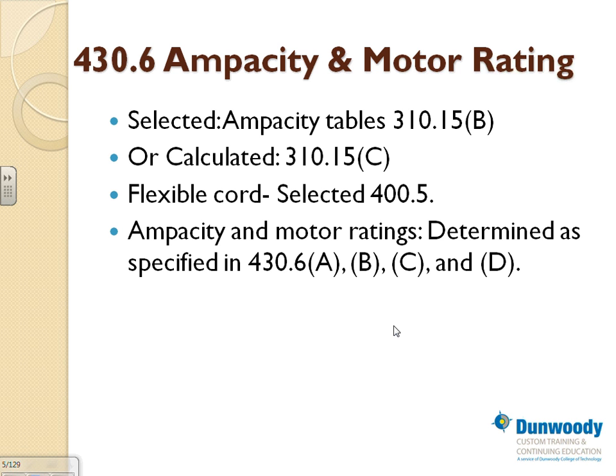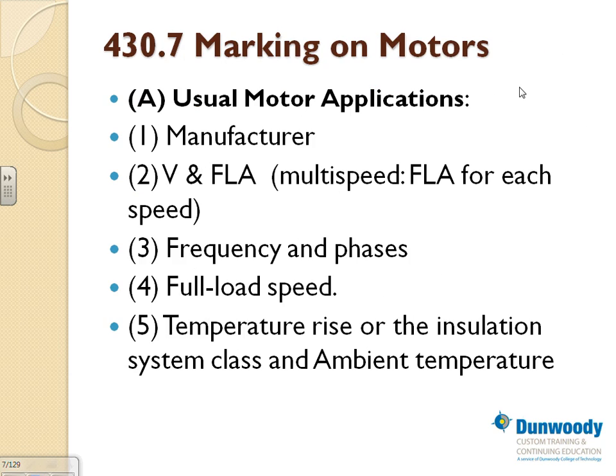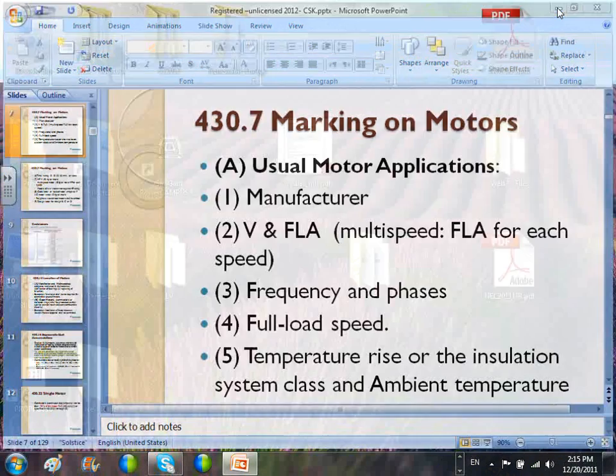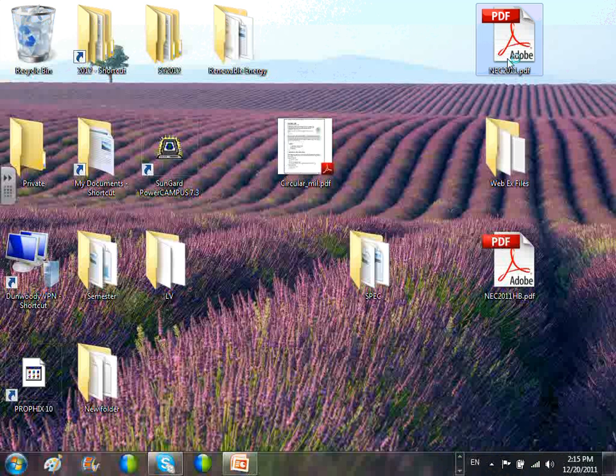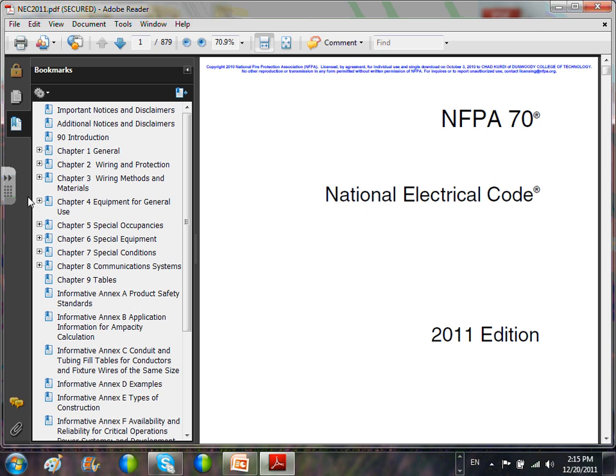When we size the equipment for motors, guys, there are tables, and in 310.15(B), you have to take the ampacity and size them based on 310.15(B)(16). Based on this table, guys, you can size the conductors for your equipment. And if you don't mind, I'll grab my NEC code book quick here.